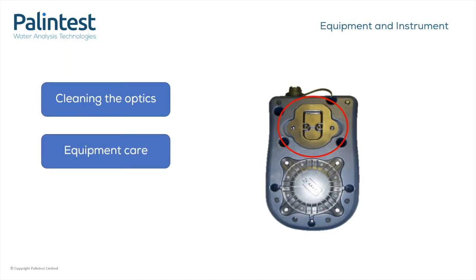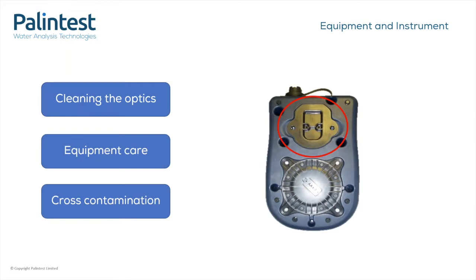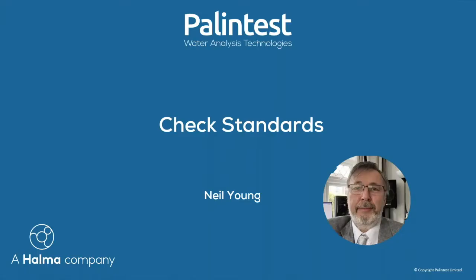Related to cleaning is the care of your equipment, and that's really your crush rods and your test tubes. Any scratches or damages on the tube will affect the reading quite significantly, so it's important to make sure that your tubes are free of scratches, fingerprints, and bubbles. We advise that you would check your tubes weekly and replace any that have any damage to them. This is also a great time to ensure that there is no cross-contamination. Any discolouration of rods or tubes shows that they are likely contaminated with chemicals from a previous test. Best practice is to wash these weekly in a weak detergent solution, and it's important to ensure that you rinse these properly and dry them before you store them. Same goes for any crush rods. We would advise you replacing anything that is still discoloured after you've cleaned it. And with that, I'll hand it back to Neil.